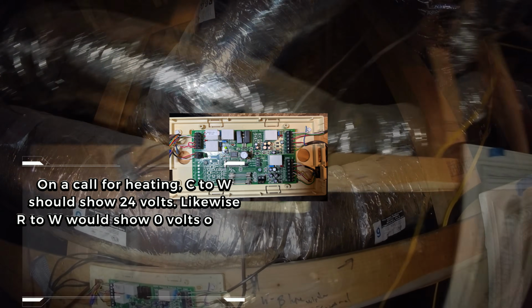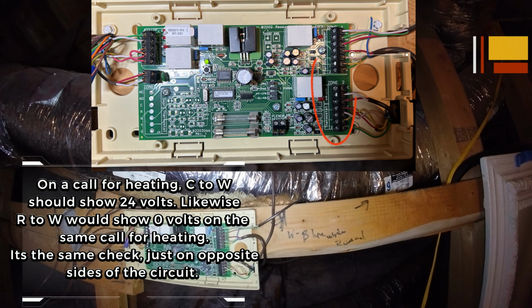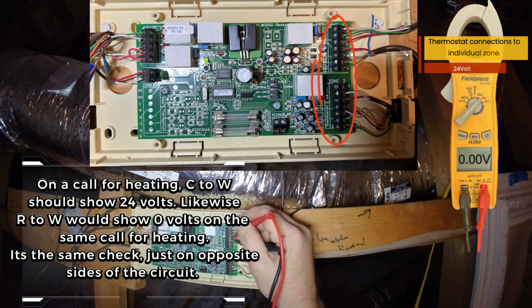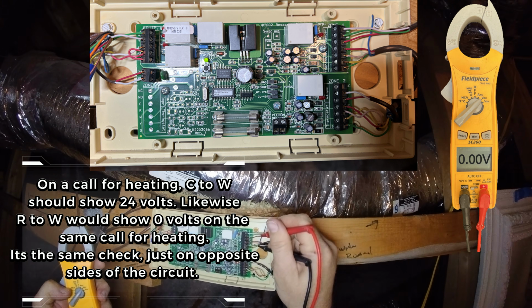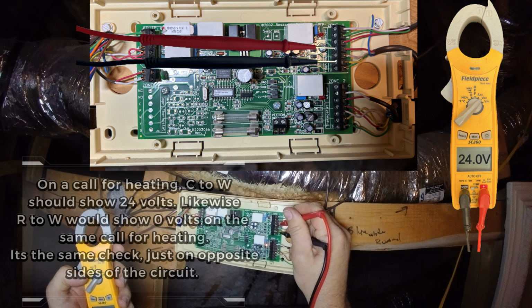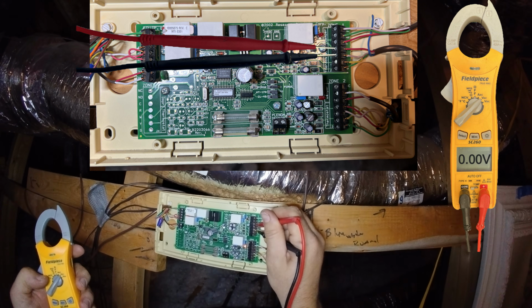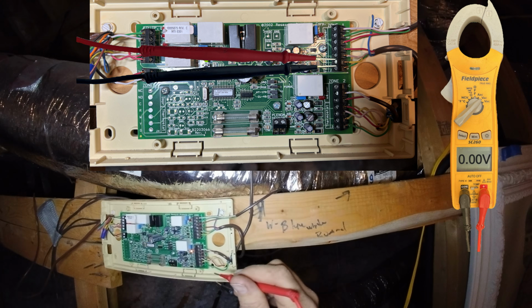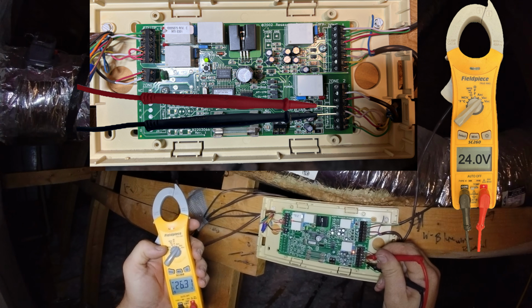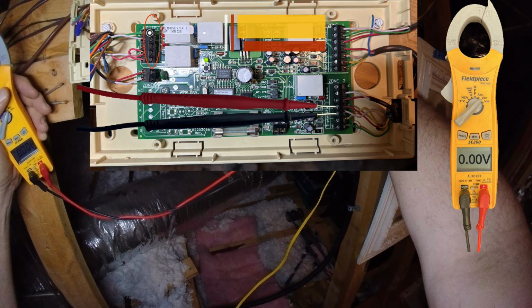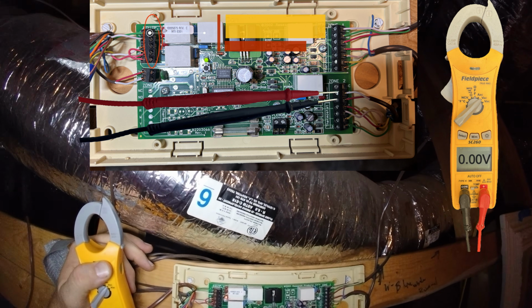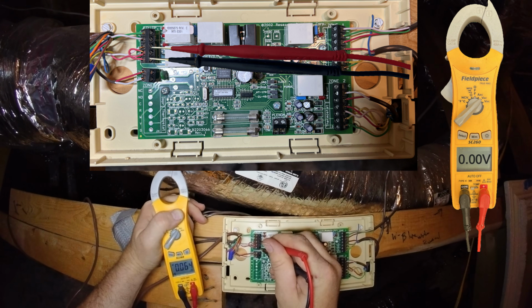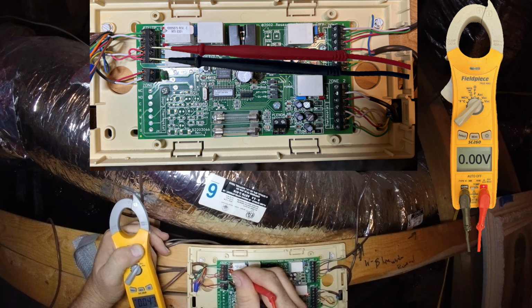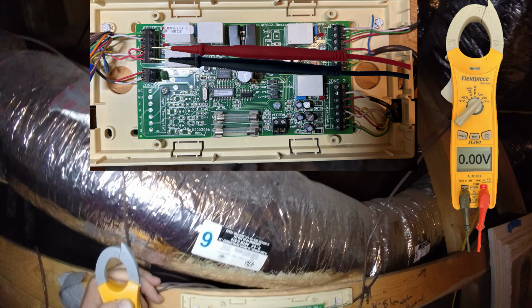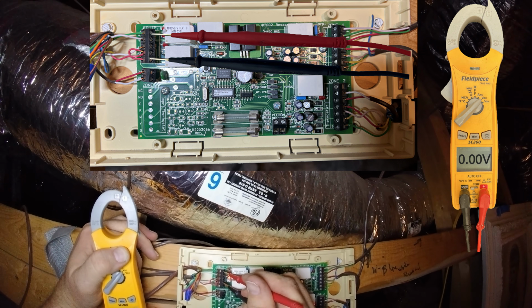We see right away we at least have power to our zone board. We check between yellow and red. We have 24 volts because it is not calling. White to red is calling, so 0 volts. Check here as well. That zone is not running. So over on our equipment side, same thing. We'll check between red and white to see if it has got a call for heating. We have nothing on this end.